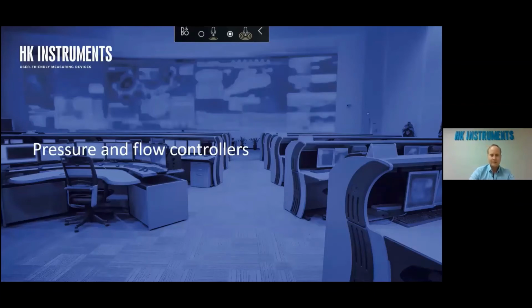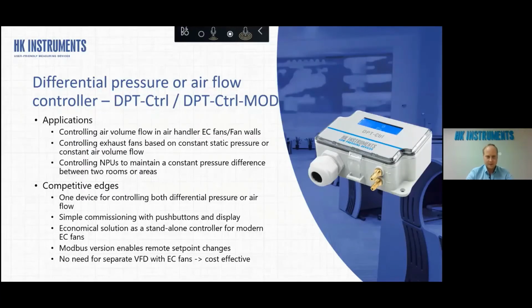Then we will take a look at the latest development for the DPT product line. So the DPT control or the DPT control mod. It's basically a similar user interface as was in the DPT flow, the airflow transmitter, but in addition to that we can measure the airflow or the differential pressure, we can also control it. So this has a 0 to 10 voltage control output that you can connect, for example, to air handling unit EC fan or fan walls. And or also you can use it for exhaust fans based on constant static pressure or air volume flow.